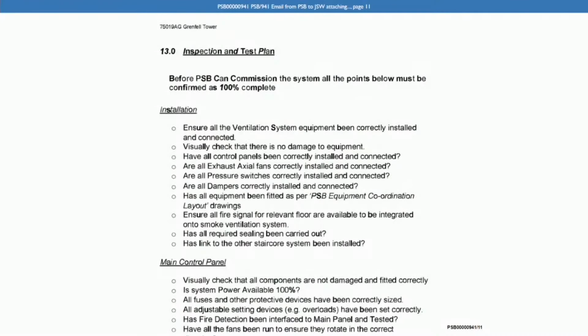At section 13, we can see there is an inspection and test plan, that's the heading at the top of the page, with a list of tasks. And it says underneath, before PSB can commission the system, all the points below must be confirmed as 100% complete. And we've then got a list of tasks. For example, under installation, it says, ensure all the ventilation system equipment has been correctly installed and connected, visually check there's no damage to equipment, have all control panels been correctly installed and connected. So was that effectively a checklist of installation tasks that needed to be completed prior to commissioning? Yes, basically.